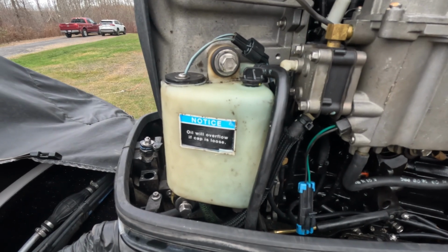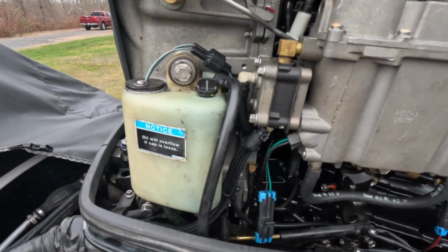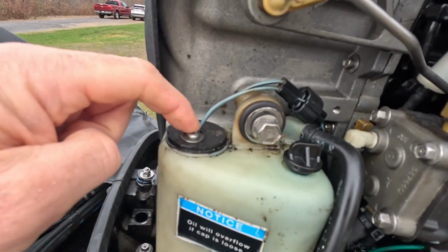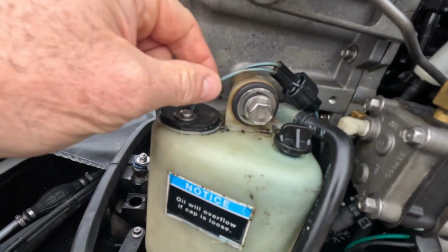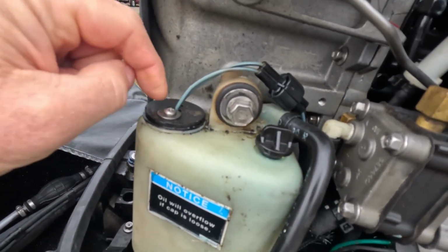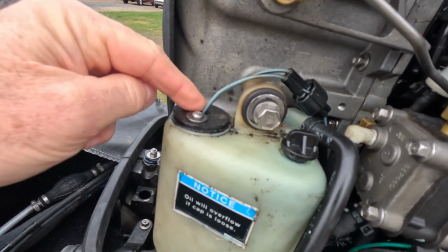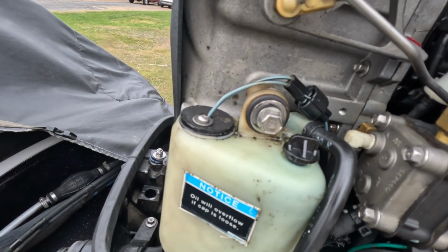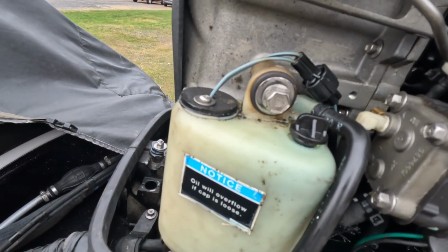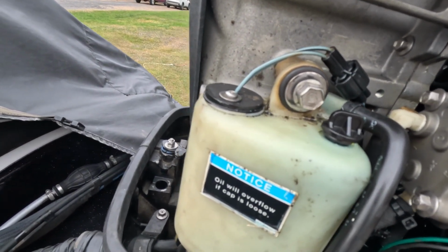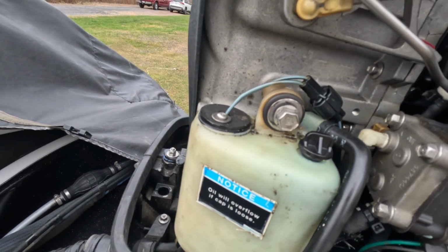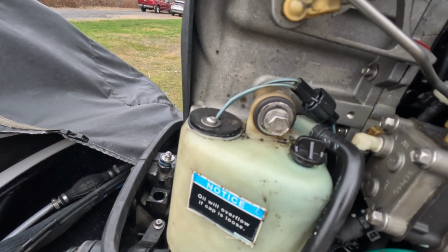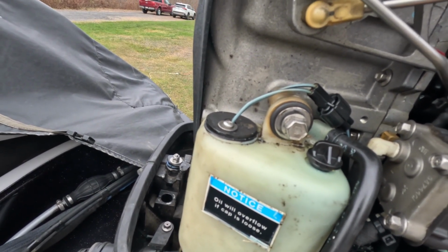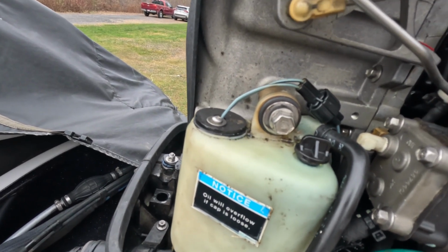An easy way to test that, I'll tell you to start with, is if you take this screw off right here, it allows you to pull this. These 2 wires are connected to a sensor probe. It allows you to pull that sensor probe out, and then what you can do is take a magnet and put it on that sensor probe. It's got to be a decent size magnet.